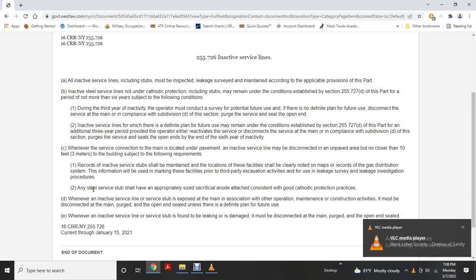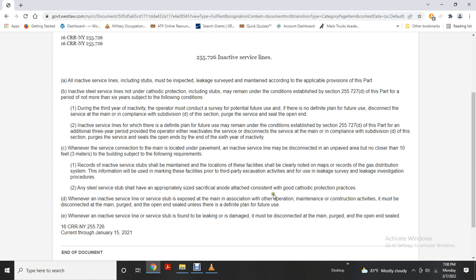Any steel service stub shall have an appropriately sized sacrificial anode attached, consistent with good cathodic protection practices. Whenever an inactive service line or service stub is exposed at the main in association with other operation, maintenance, and construction activities, it must be disconnected at the main, purged, and the open end sealed, unless there is a definite plan for future use. Whenever an inactive service line or service stub is found leaking or damaged, it must be disconnected at the main, purged, and the open end sealed.